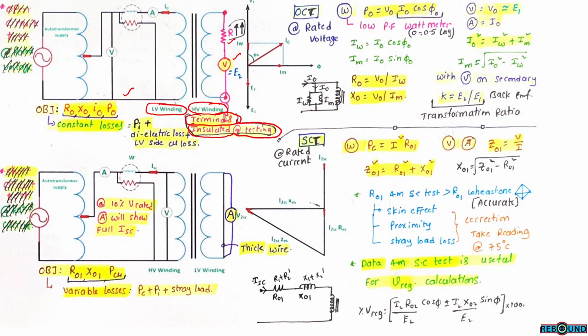The main objective of this open circuit test is finding R0, X0, I0 and P0. P0 is the no load losses. So from this open circuit test, we get the constant losses, the total iron losses and dielectric losses. Primary side copper losses are very small.